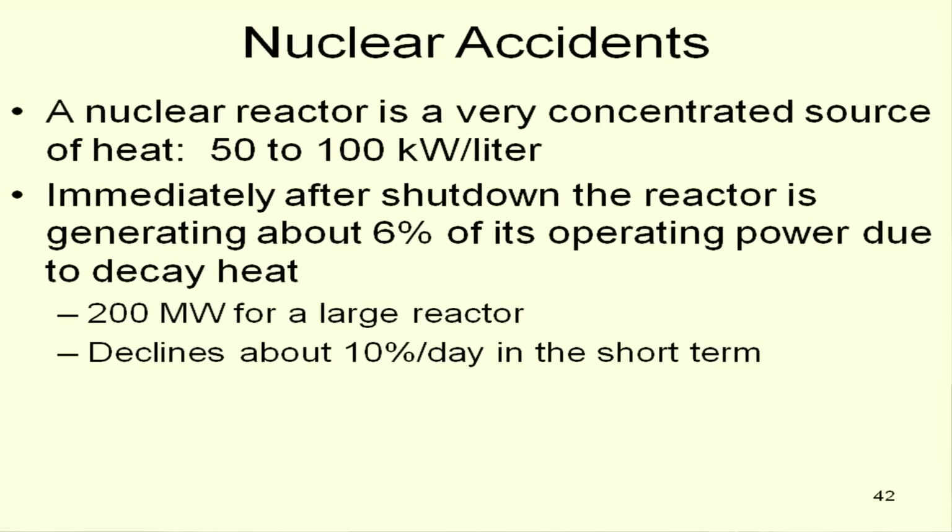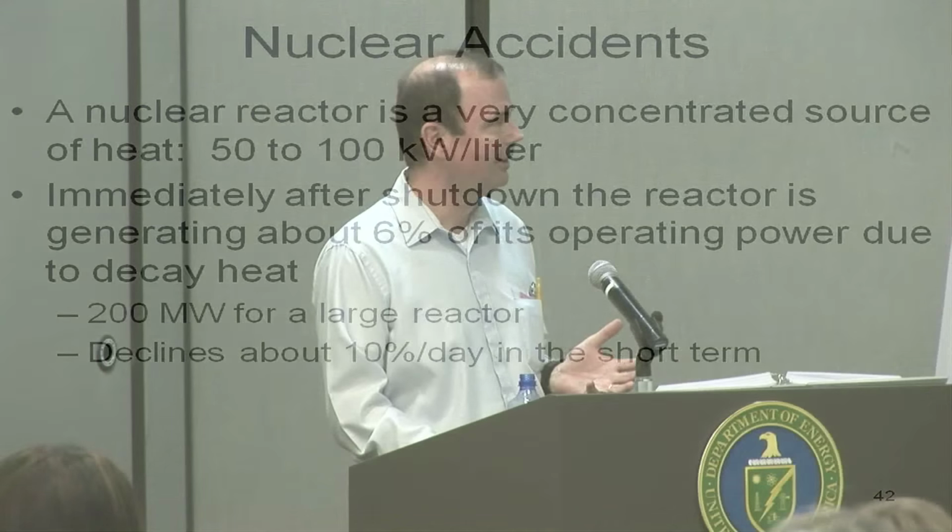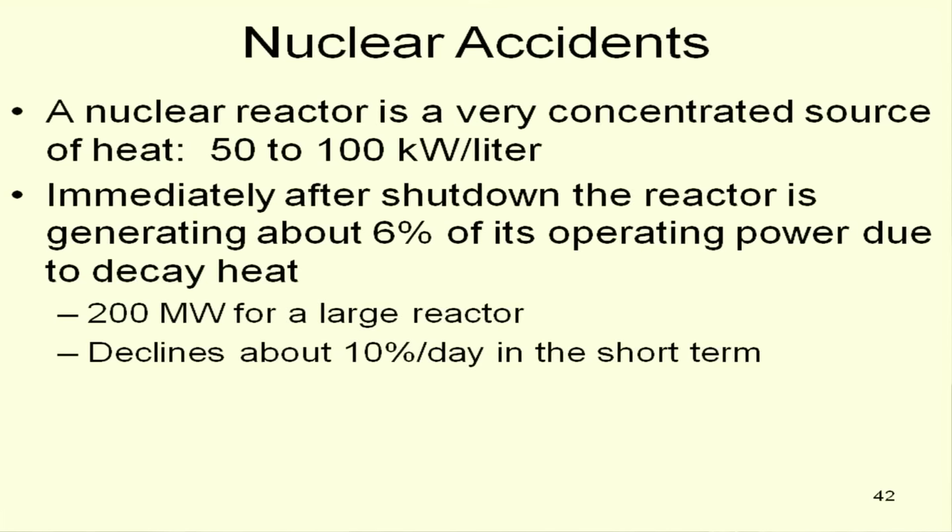Okay, talk a little bit about some nuclear accidents here. A nuclear reactor is very concentrated, and in a liter, which is like a quart, you're generating 50 to 100 kilowatts of thermal power. That's a fair amount of energy in a local place, so you've got to keep removing the heat. Even if you shut down the reactor, just scram it instantaneously, you're still generating heat at about a 6% rate, which is a couple hundred megawatts for a large reactor.